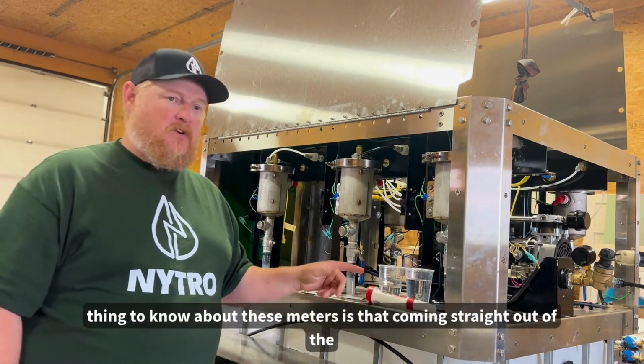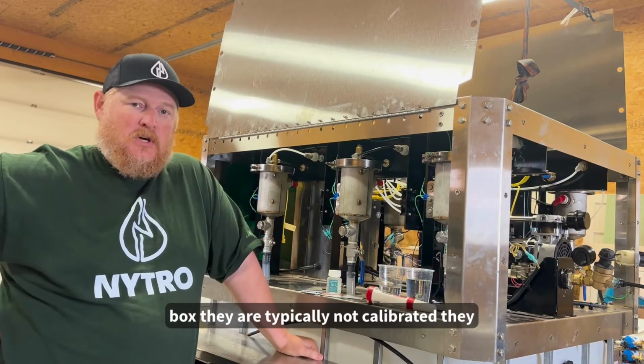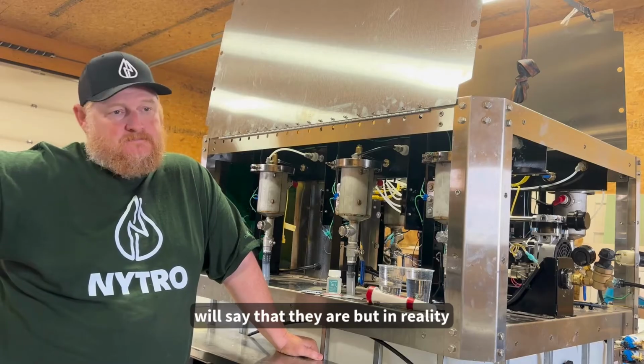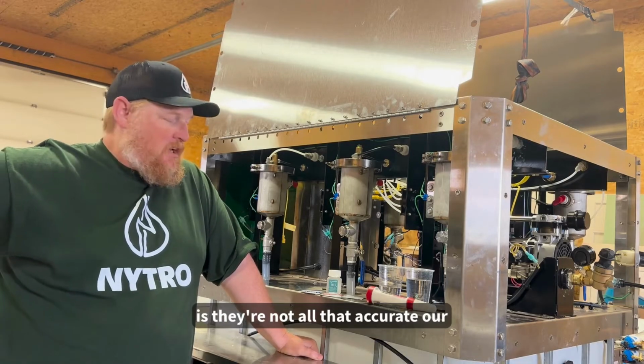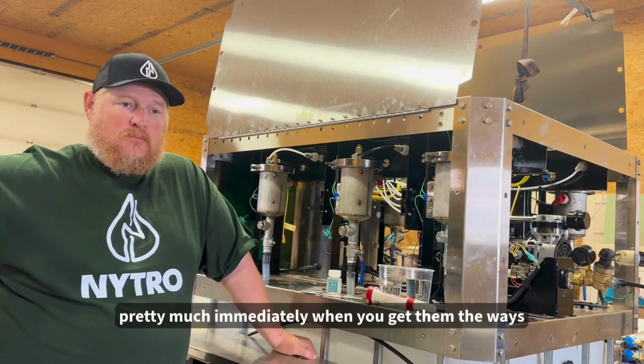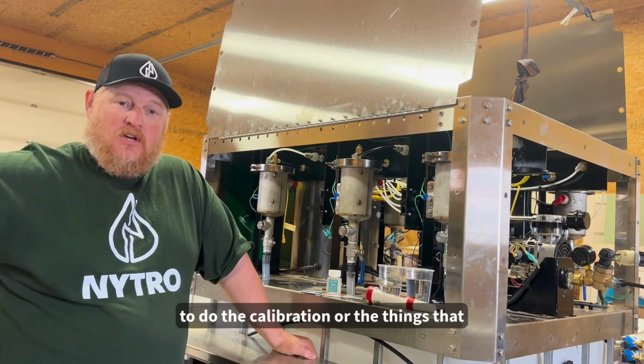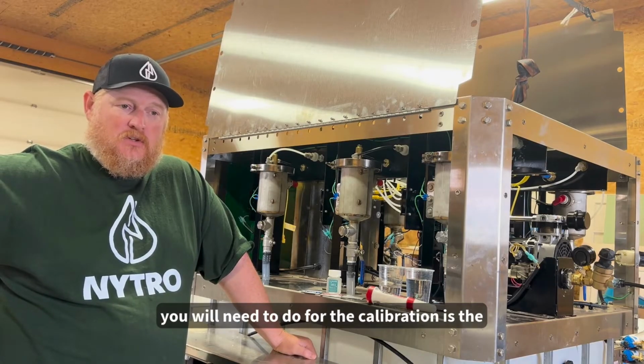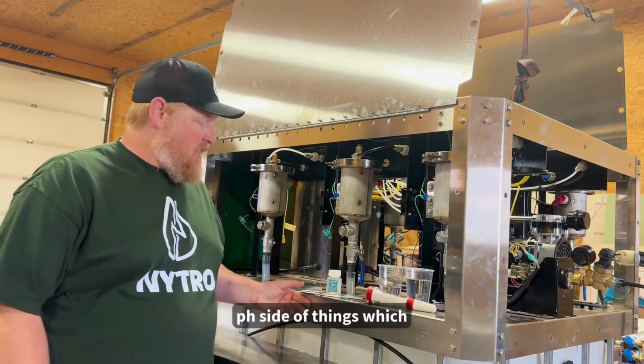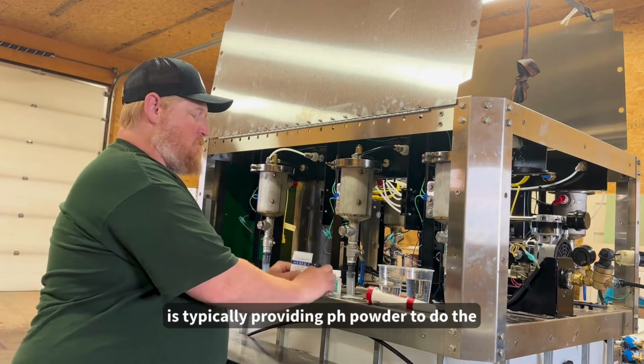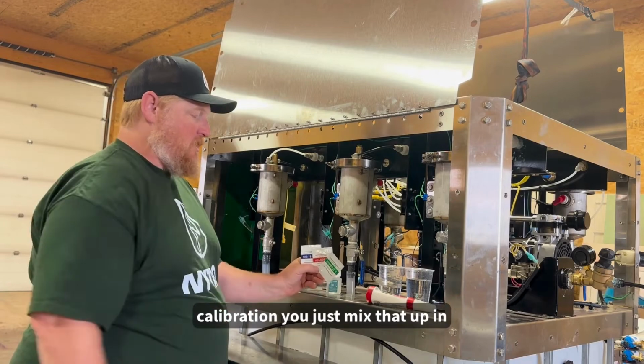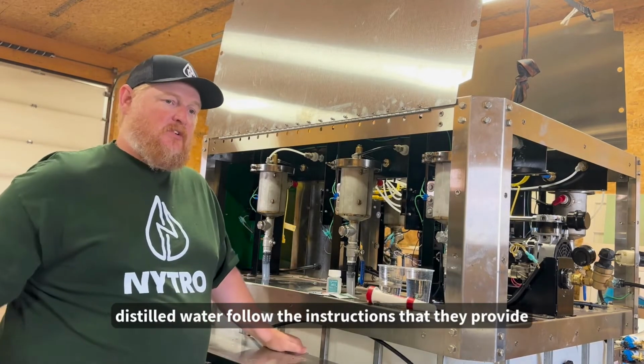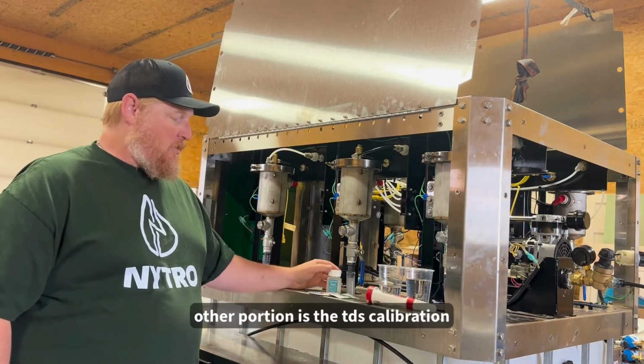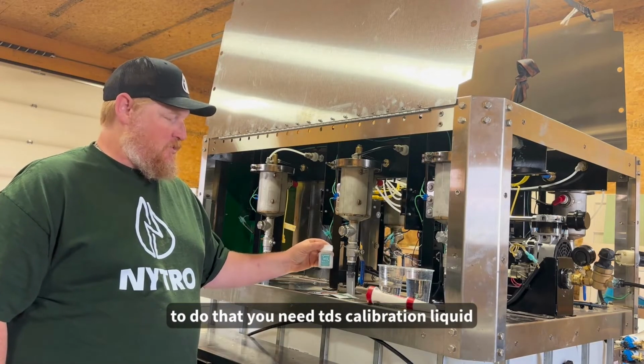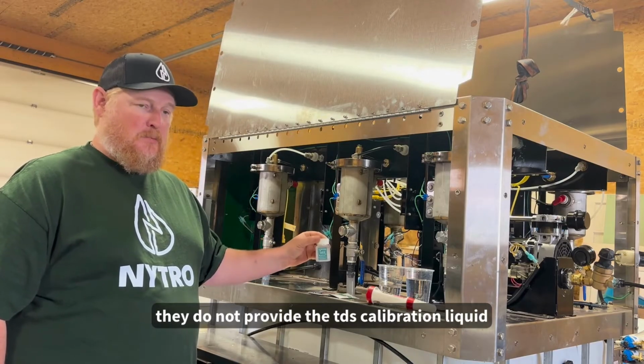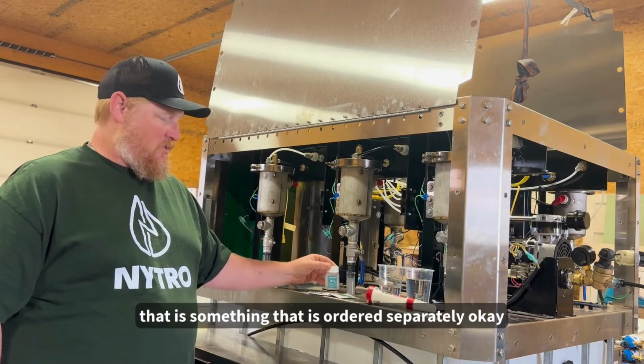The thing to know about these meters is that coming straight out of the box, they are typically not calibrated. They will say that they are, but in reality, they're not all that accurate. Our recommendation is to calibrate them pretty much immediately when you get them. For the pH side of things, they typically provide you pH powder to do the calibration. You just mix that up in distilled water, follow the instructions that they provide, and that will get you where you need to be. The other portion is the TDS calibration. To do that, you need TDS calibration liquid. They do not provide the TDS calibration liquid. That is something that is ordered separately.